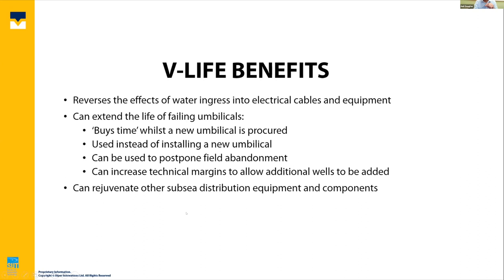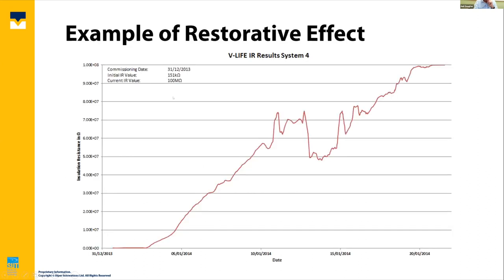So as I said, let's just show you a picture of a real system. This is one of our early installations, but I've had this slide for many years and I haven't bothered changing it. You can see up here that the original insulation resistance value is 150 kilo-ohms. It was installed over Christmas in 2013, turned on just into the new year. And this is a trend of the measured insulation resistance. You can see within 3 weeks, we got up to 100 mega ohms. So that is quite a significant increase in a very short period of time.